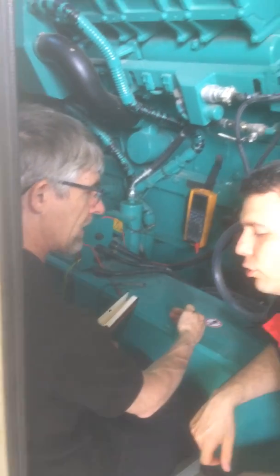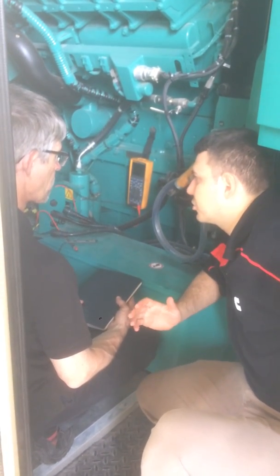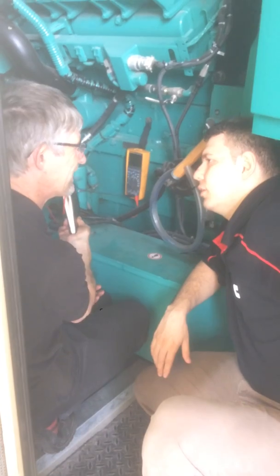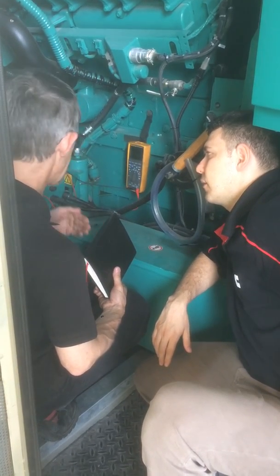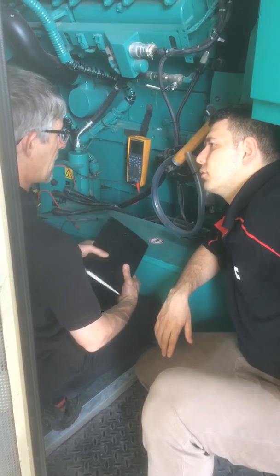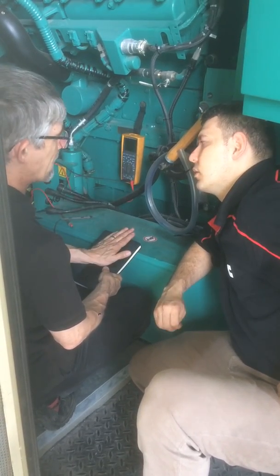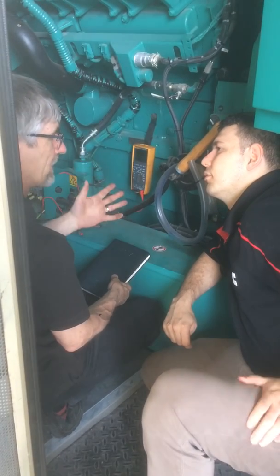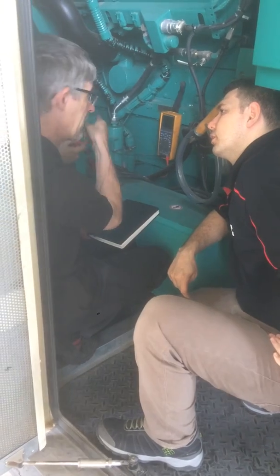As an action point: we will change this heater and then monitor it. I will translate for those who don't speak English. If you'd like to make any other checks we can do that. I can see by these readings there's a problem with this one — you've had problems with that one. So we change the heater and keep monitoring. We don't have fast-blow fuses in. Keep the fuses as they are, fuse holders good. I will put a request in for it to be investigated. Next time we do a service, check the fuse holders and check with the customer if there are any problems.